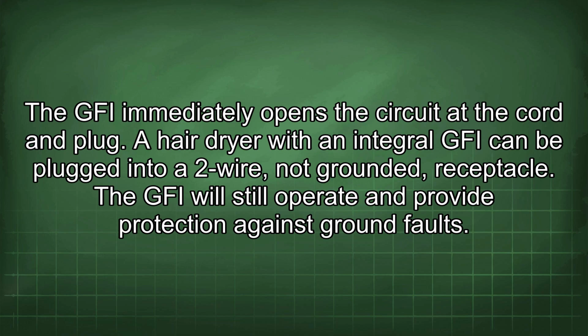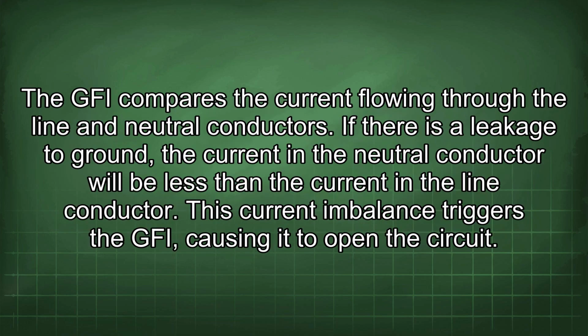A hairdryer with an integral GFI can be plugged into a 2-wire, not grounded, receptacle. The GFI will still operate and provide protection against ground faults. The GFI compares the current flowing through the line and neutral conductors. If there is a leakage to ground, the current in the neutral conductor will be less than the current in the line conductor. This current imbalance triggers the GFI, causing it to open the circuit.